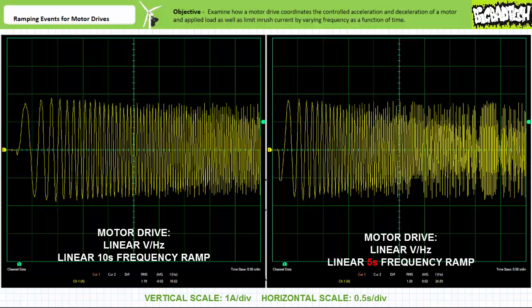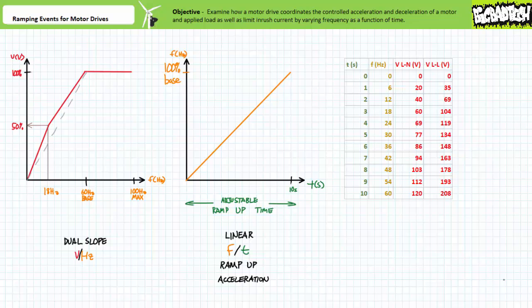This analysis is a little more complicated when the motor drive is capable of using more complicated volts per hertz profiles, such as a dual-slope torque boost volts per hertz profile — however, not impossible. Assuming a base frequency of 60 hertz and a plus 20% voltage boost at 30% of the base frequency, or 18 hertz, and the same linear acceleration profile where excitation frequency is ramped up to 100% of the base frequency over an adjustable acceleration time of, let's say, 10 seconds, one can calculate applied voltage and excitation frequency at specific times.